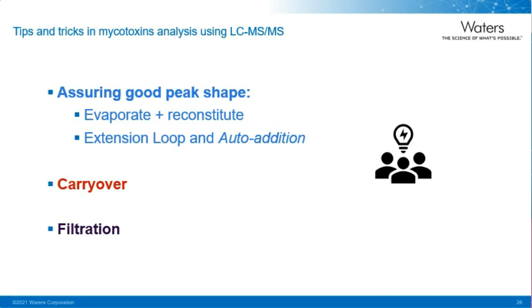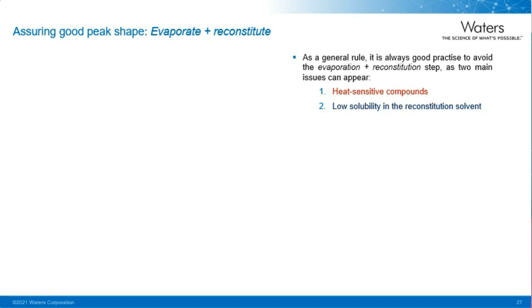The evaporation and reconstitution step is often performed prior to LC analysis, as this is a way to match the solvent composition of the diluent with that of the initial mobile phase. Also because it is an effective way to concentrate the sample. However, many times, especially in multi-residue methods, some compounds produce a loss of recovery due to two main reasons. They can be volatile or degrade with the extra heat, and they don't fully solubilize in the reconstitution solvent, mainly water.